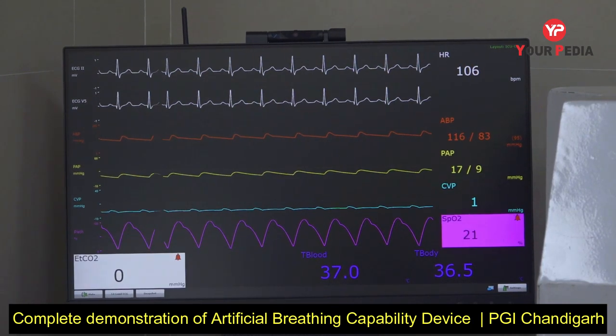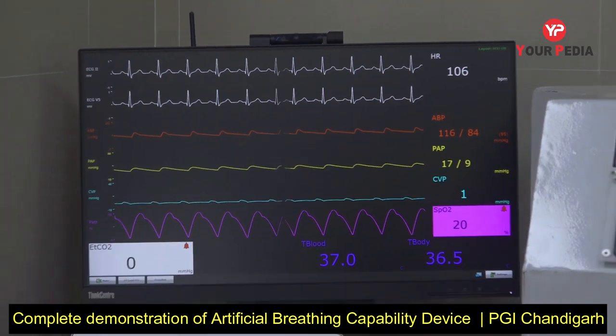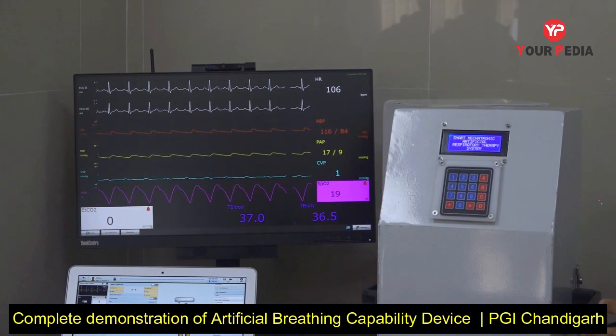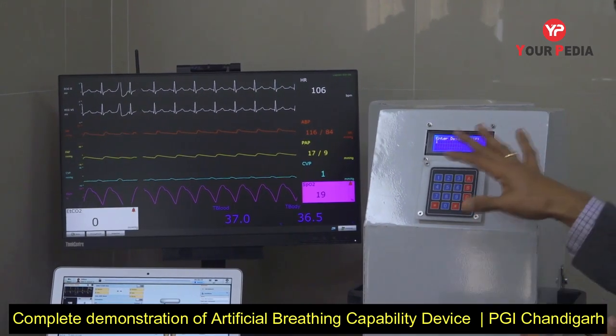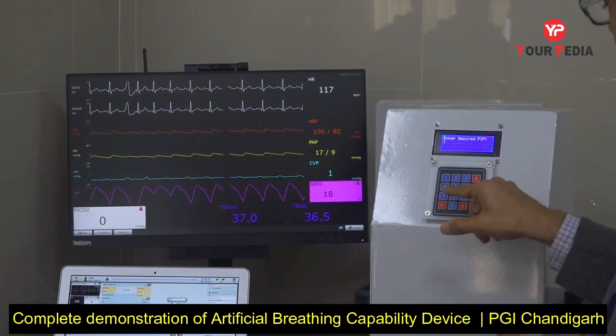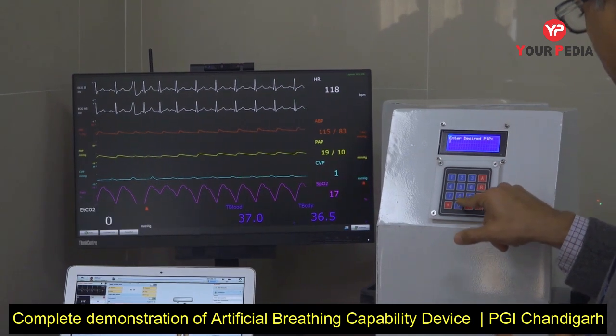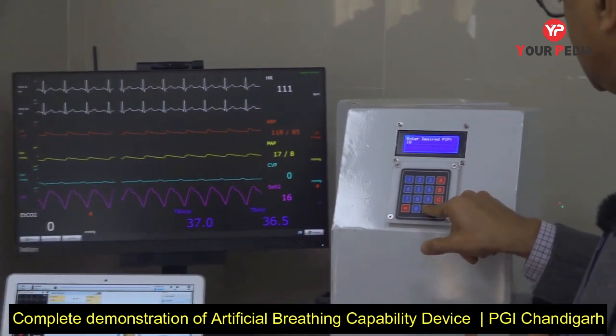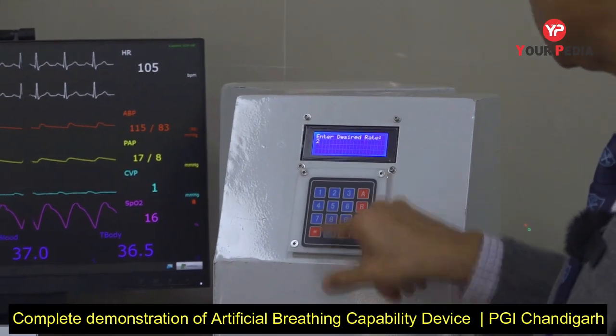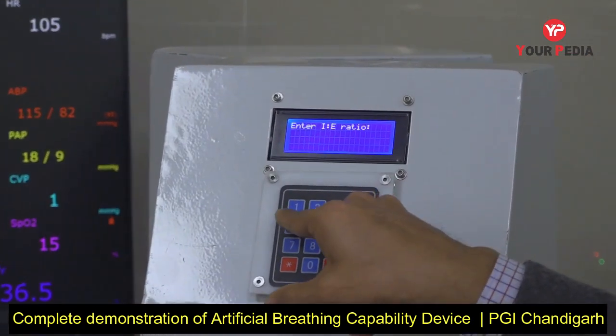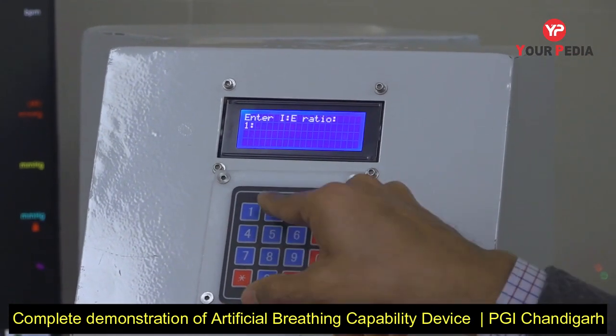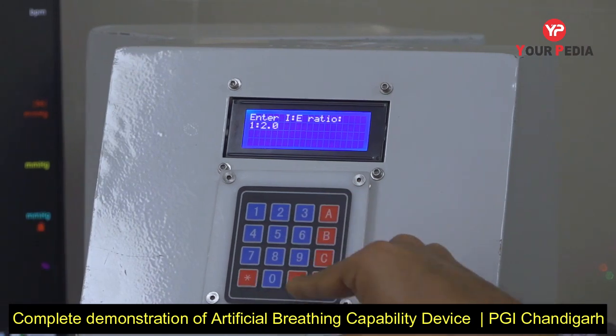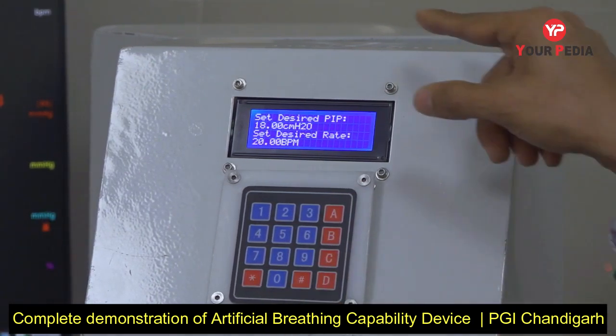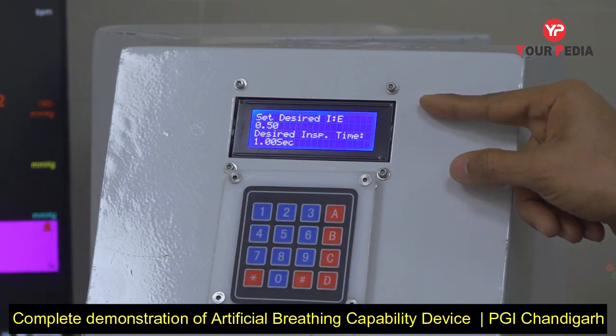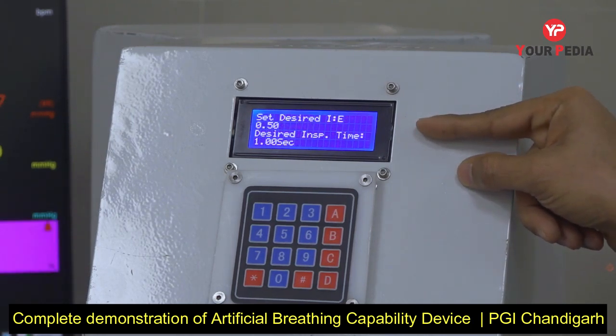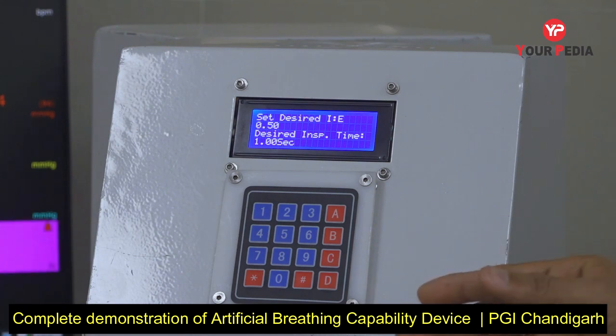Say here I'm giving a demonstration of operating this device to support a patient's respiration. So this device allows us to enter an inspiratory pressure. I'm entering here an inspiratory pressure of 18, a desired rate of approximately 20, and an IE ratio of 1:2.0, which is what we would use in patients like this. The device immediately displays the parameters which have been set, calculates the inspiratory time, and at once starts delivering.